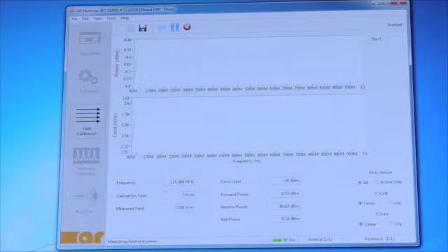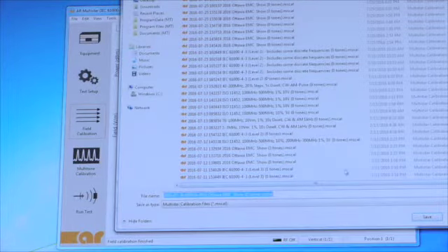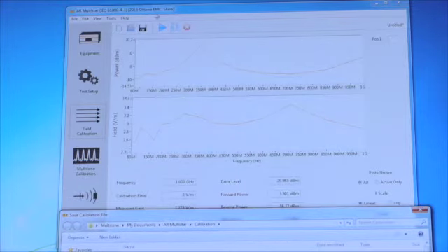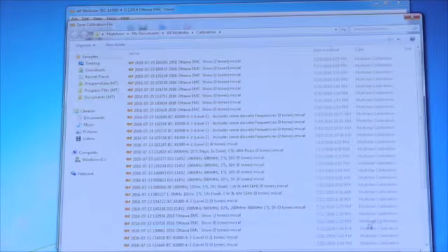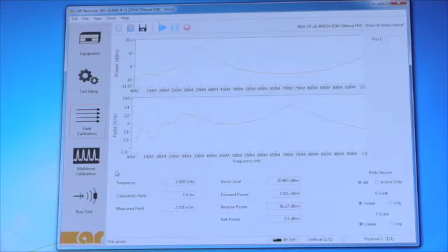So now what it's doing, it's stepping through the frequency steps at 20% steps at a field of 3 volts per meter. And it's recording the measured field, and it records it in this screen here. And it records how much power you need, right, in here. So you have that all recorded, and then you can save that file. Once you have that file calibrated for single tones, you're ready to do the tone set calibration.